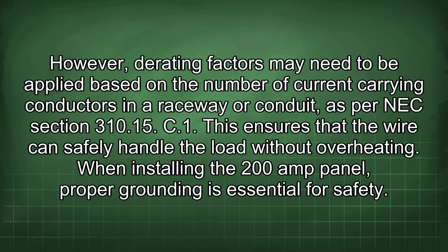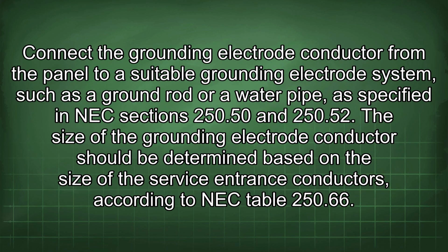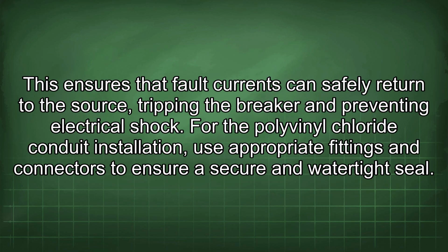When installing the 200 amp panel, proper grounding is essential for safety. Connect the grounding electrode conductor from the panel to a suitable grounding electrode system, such as a ground rod or a water pipe, as specified in NEC sections 250.50 and 250.52. The size of the grounding electrode conductor should be determined based on the size of the service entrance conductors according to NEC Table 250.66. This ensures that fault currents can safely return to the source, tripping the breaker and preventing electrical shock.